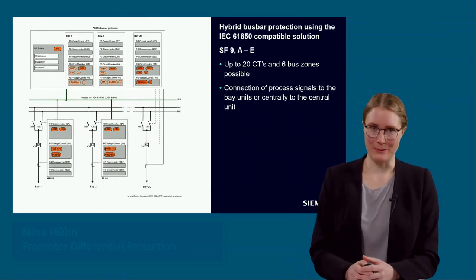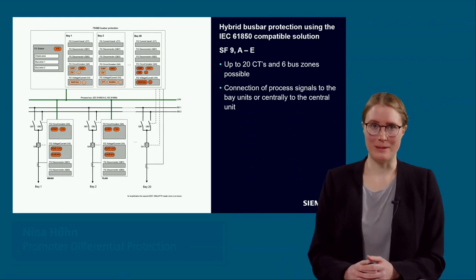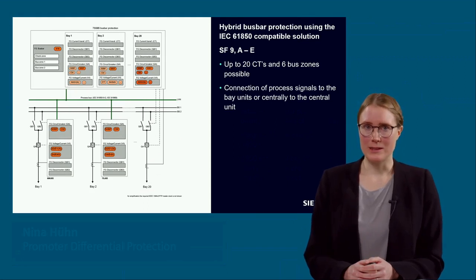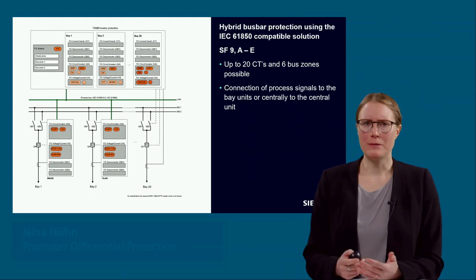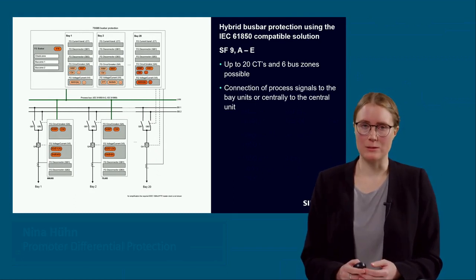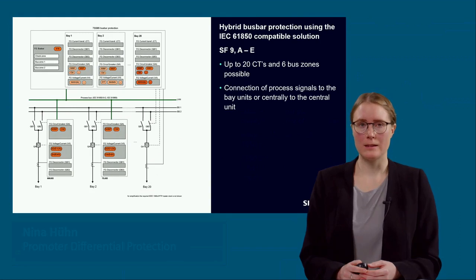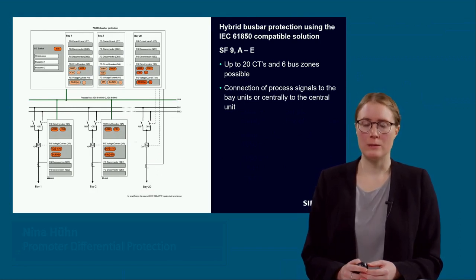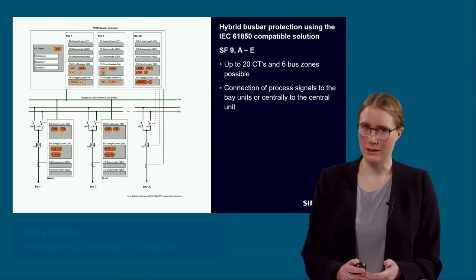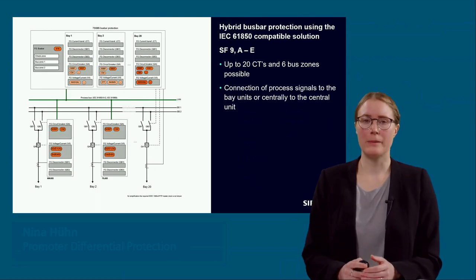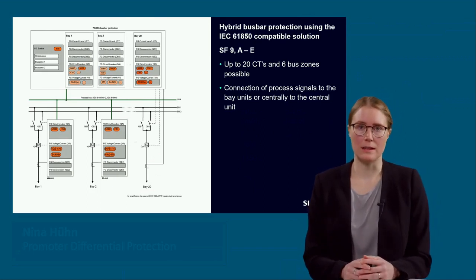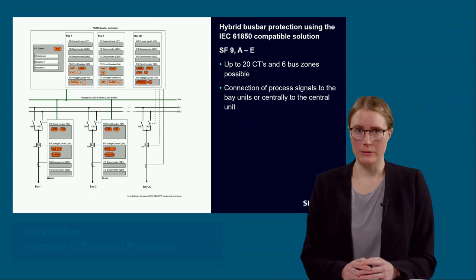Okay, this slide shows a hybrid busbar protection system using the IEC 61850 compliance solution as well. Hybrid means in this case that you have merging units for some bays in the field, and some of the process signals are directly connected to the 7SS85. This hybrid setup is only possible with the IEC 61850 compliance solution. In this sketch, bay 1 and bay 2 are connected to merging units, and bay 20 is connected directly to the 7SS85. For the hybrid setup, only up to 20 measuring points are possible.